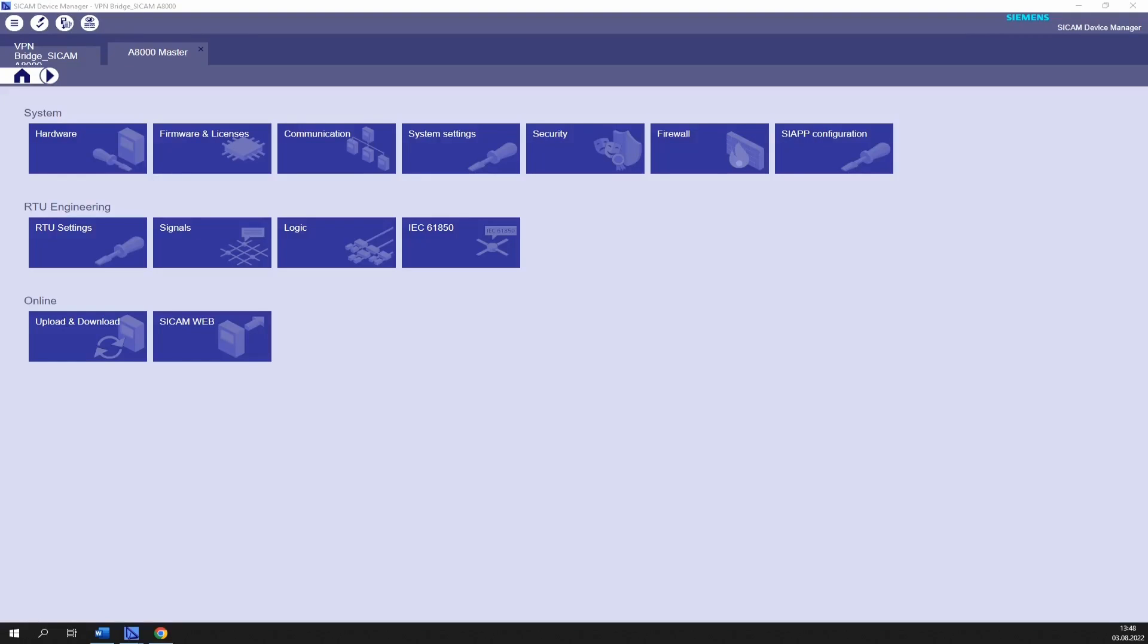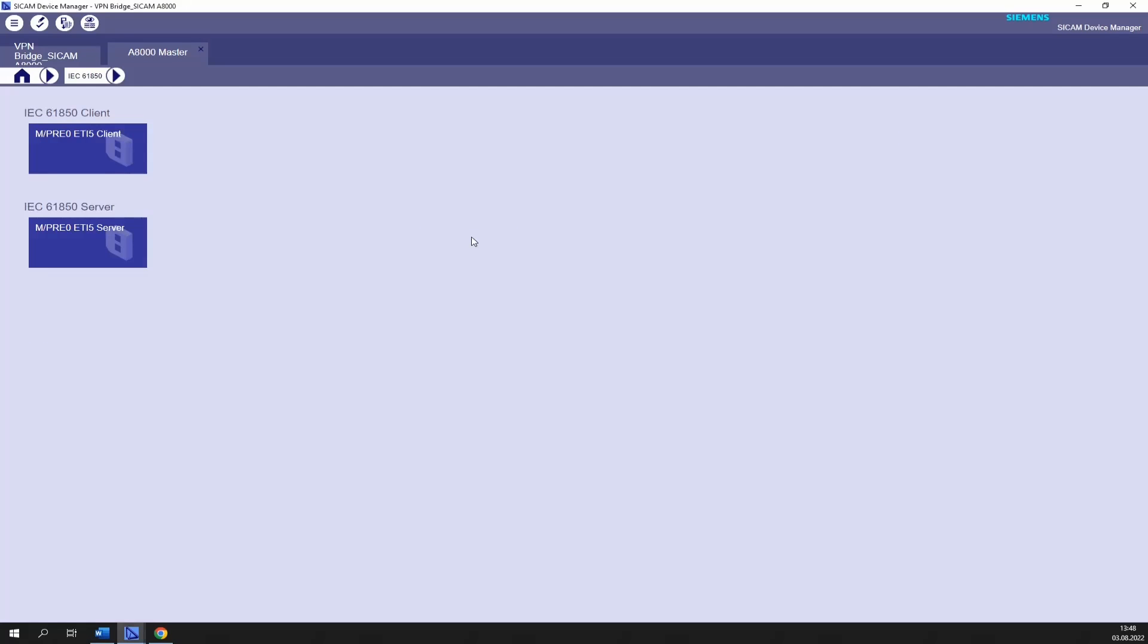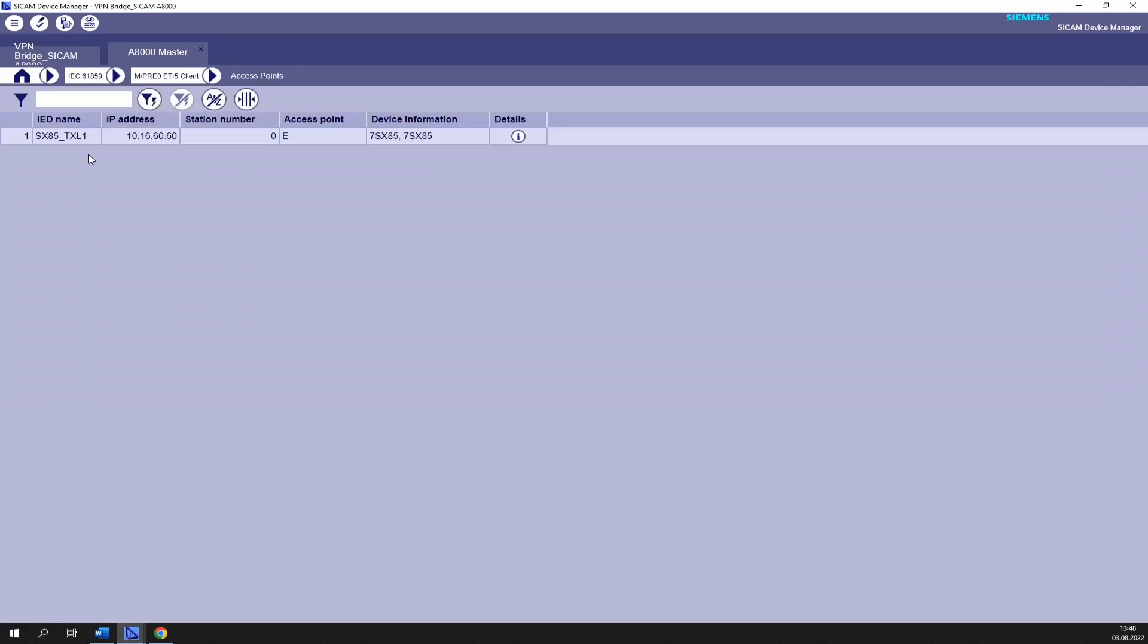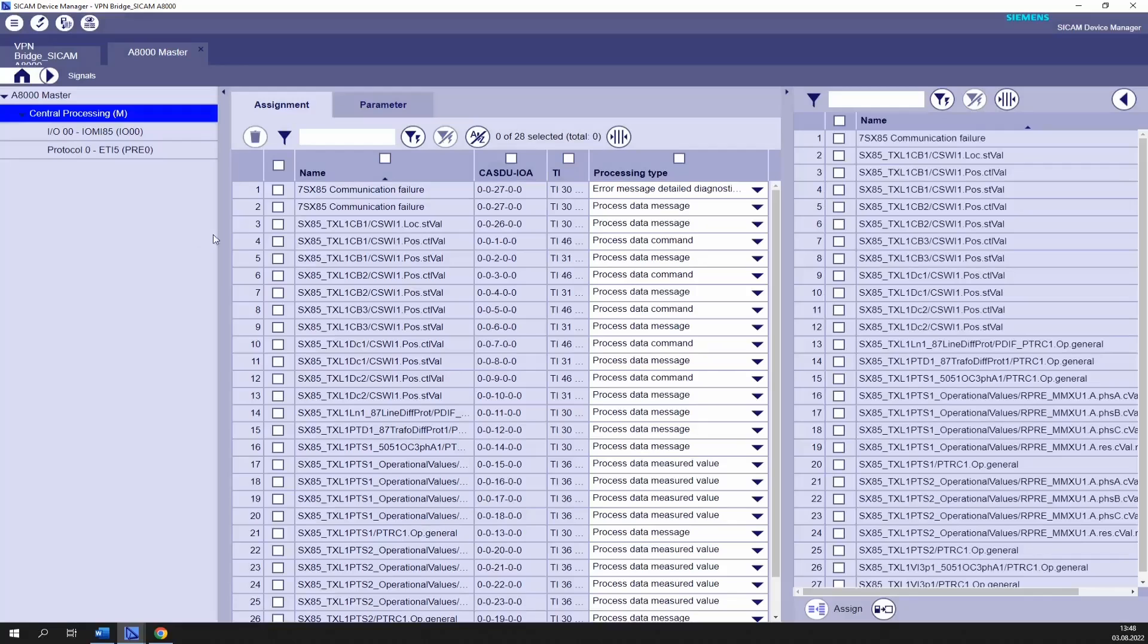Let's start with our application example. I have configured a CP8031 to communicate with our 7SX85 device simulated in the digital twin. Here in the IEC61850 editor we can see the access point with the corresponding device and IP address. And if we go to signals we can see the list of signals which have been already imported into the CP8031 configuration.